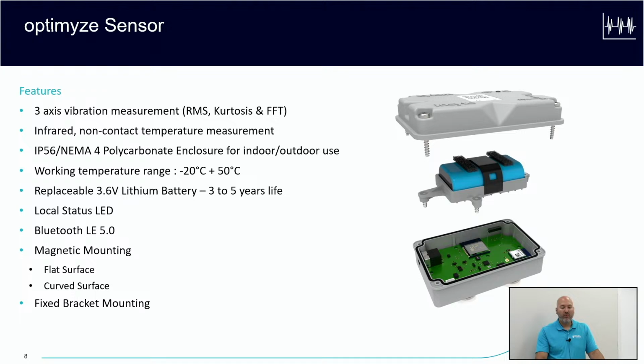So here, just an overview of the Optimyze sensor itself. It is taking vibration readings in 3 different axes. We do have on the bottom center of the sensor an infrared non-contact temperature measurement reading. There's a little port underneath there you would see that's taking the temperature readings. The Optimyze sensor itself is rated NEMA 4, so it can be used in outdoor applications.